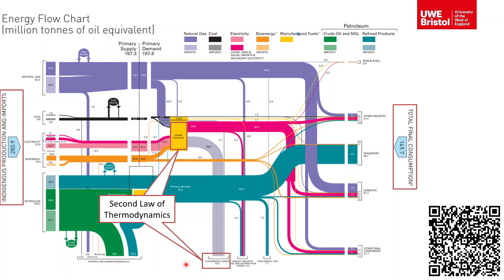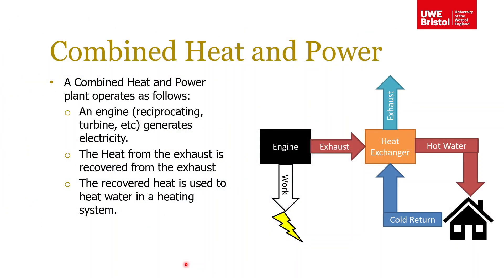That's what combined heat and power is all about. The idea of a CHP plant is that you actually recover some of that energy from the exhaust. A combined heat and power plant operates on the following principles: you have your heat engine — that could be a reciprocating engine, a turbine, or whatever — and it generates work, which you then use to produce electricity. The exhaust gases, which would normally be wasted to satisfy the second law, are instead utilised.